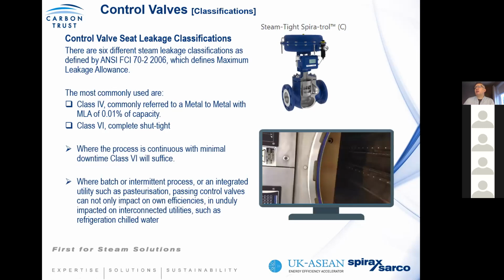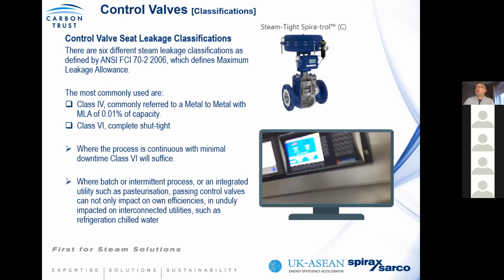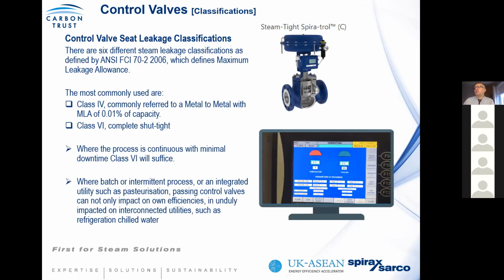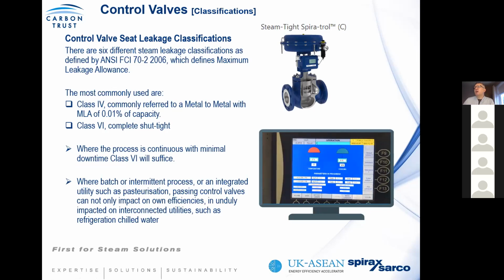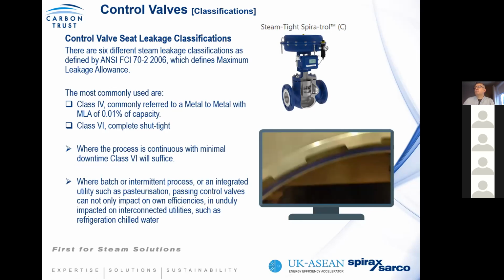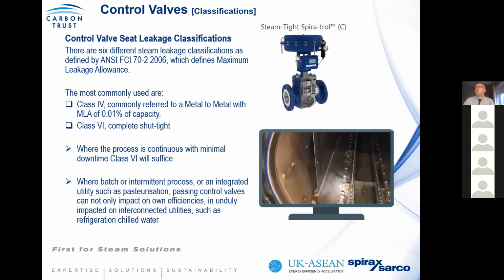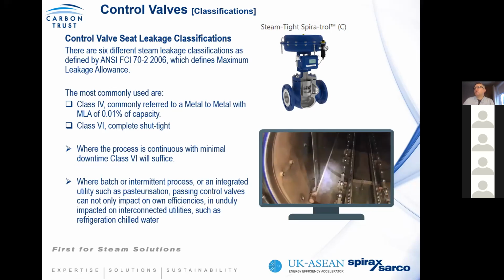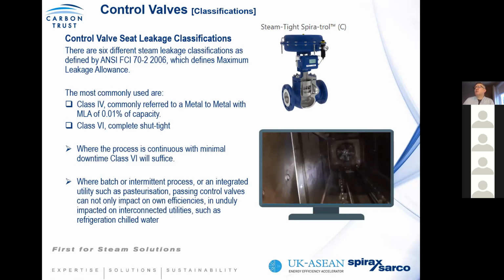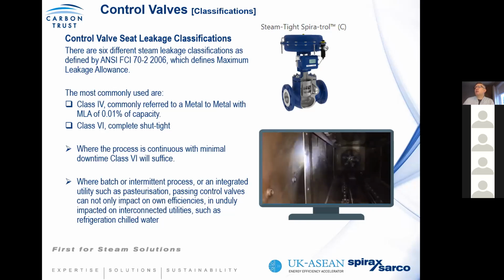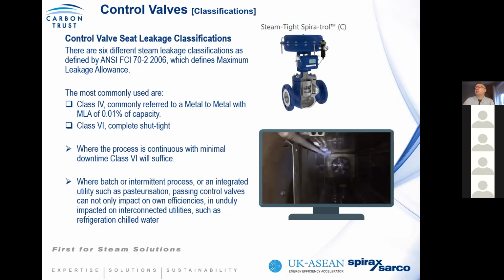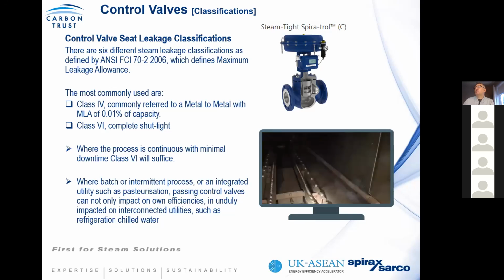Again, what I'm showing here is a little case example of a customer we visited, and you can see here that the steam valve is at 0% output. However, what you can see is that over time, his class 4 valve has effectively had the seat eroded. And you can see that we're continuously putting steam into what is an open chamber.